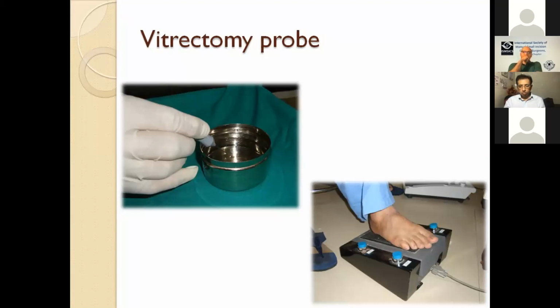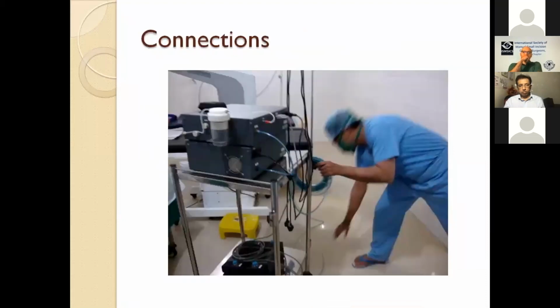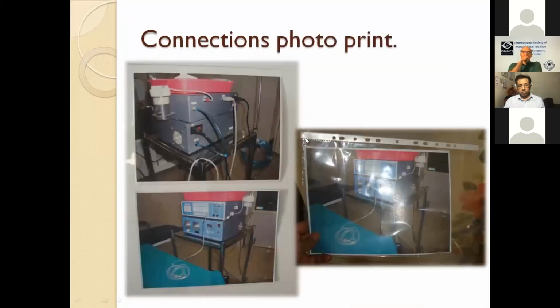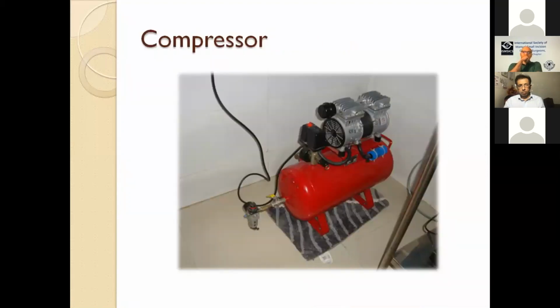Later, the same probe connections are made to the air. It is there in the front panel. I'll show you. Yes, here it is. This air injector system is there. You connect it to that, and whatever water bubbles are there inside are evacuated, and it is ready for sterilization.